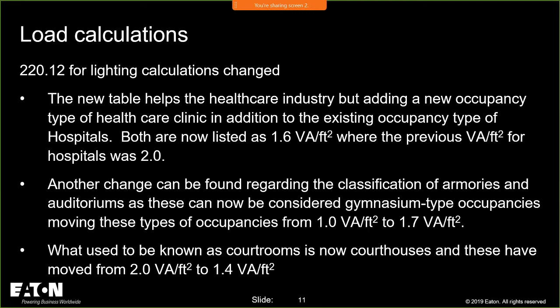We made a change, I think, in the positive for hospitals, but we had to make a different fix later in the NEC, where we removed some of the demand factors. I think it's back in table 220.42. Because of this reduction here, we had to go back to the demand factors, because this task group was very focused, it was a spreadsheet heavy effort. They were looking at where the code is today for different types of occupancies, where the latest ASHRAE code would take it from a VA per square foot calculation, and where we didn't want to lower the swamp too much. So we made adjustments here, but then we had to adjust the demand factors over in 220.42, which we're going to talk about.